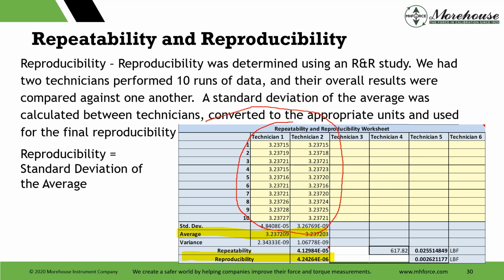Typically, if I have 5 technicians, I'm going to use all 5 technicians and do some type of R&R. If I have 6 technicians, I'm going to use 6. If it's only me, I'm probably just going to do technician 1 and I'm going to do me again in general. I know some labs have that. And then I'm going to figure out what that reproducibility condition is. If it's really high, it could be something, maybe my force equipment. Maybe it's the device I'm using. Maybe I have some side load. Maybe it's not really plumb level, square, and rigid as it needs to be.